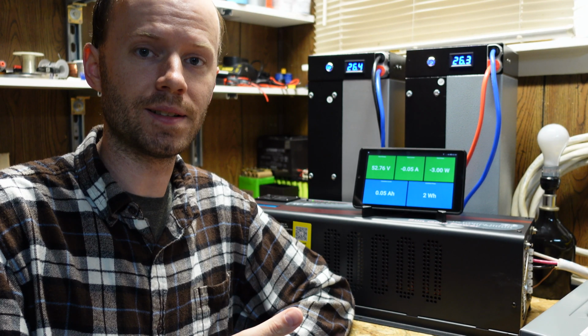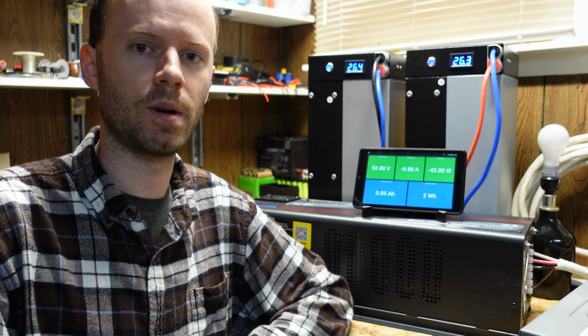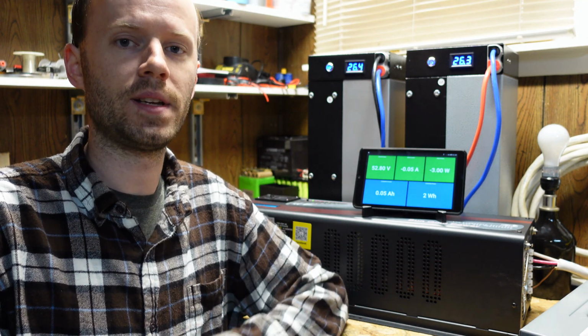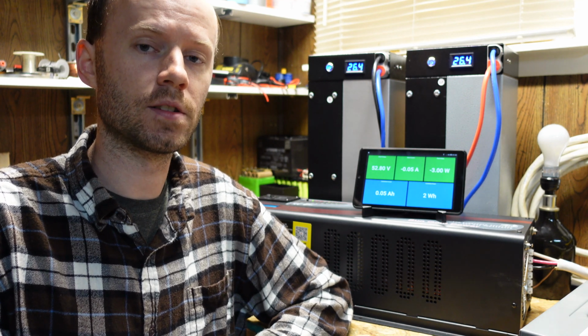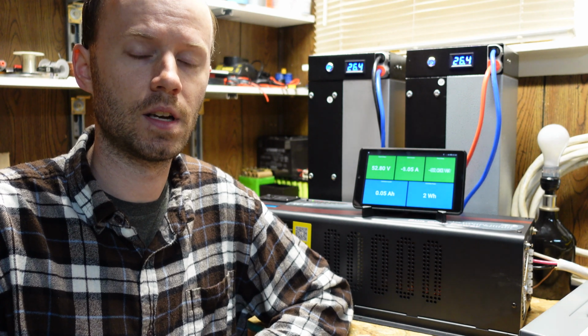That's pretty cool, right? It saves a lot of power that way because the inverter's not running when there are no loads connected. Not quite yet. The way this works is you need to have a load of at least 25 watts or greater for the inverter to detect it and turn on. Additionally, it's only checking for a load on one of the two legs. So if you don't have the load connected to the right leg, it's not going to see that load and it's not going to turn on.